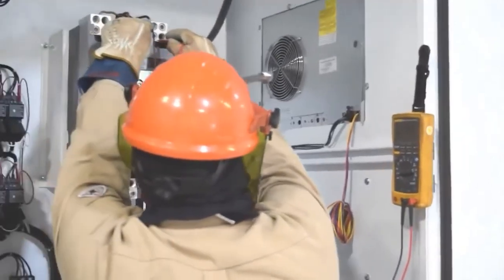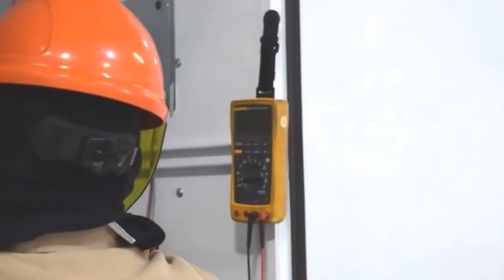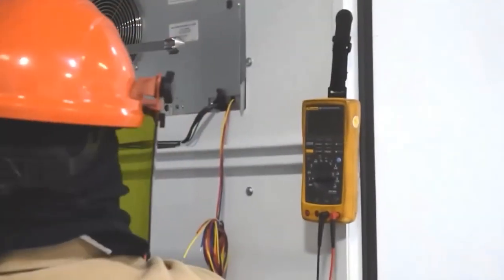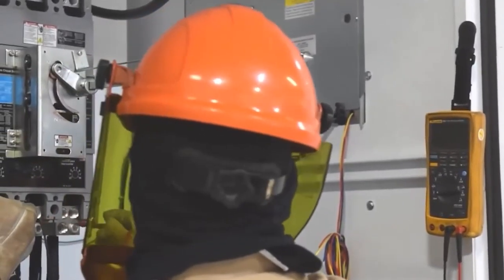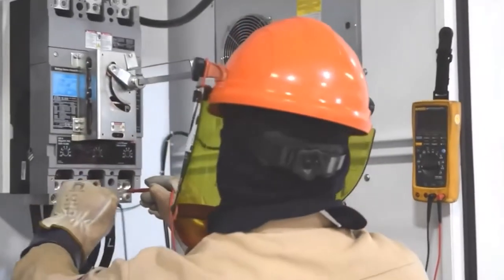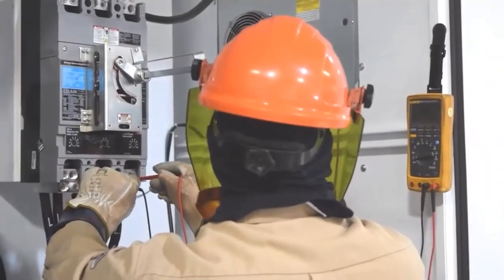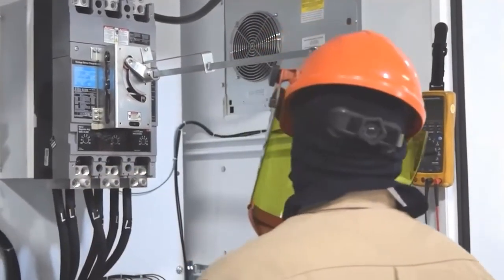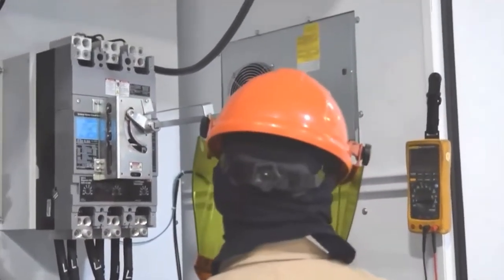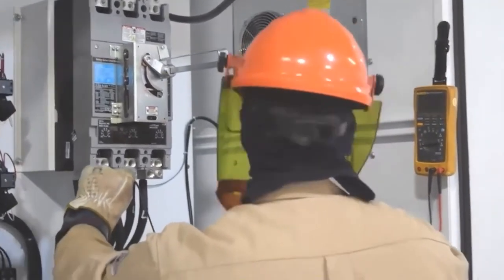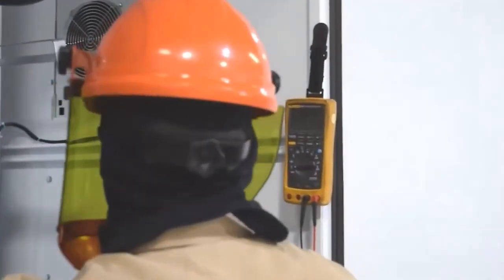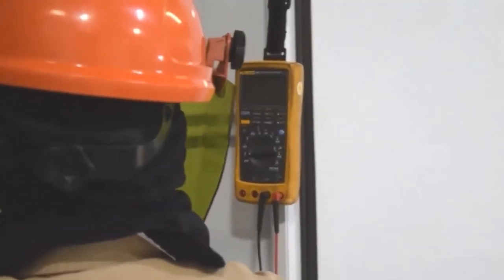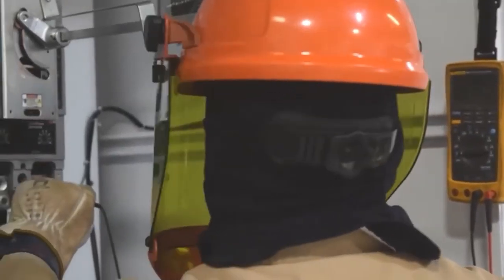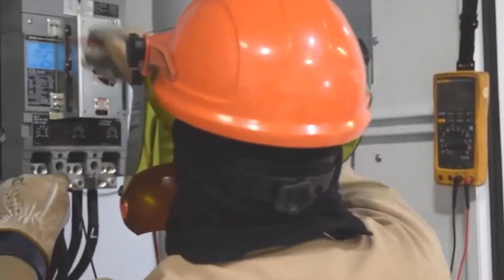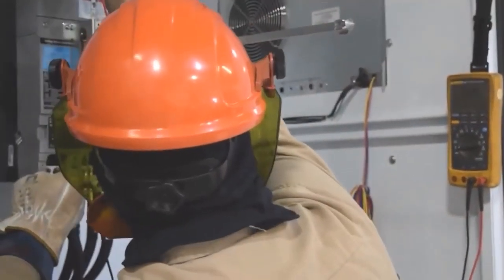So I measure from A to B, B to C, C to A. Should get a pretty normal reading. In our shop, I'm running about 489 or so. I'm going to measure in the front of the breaker and on the bottom of the breaker, just to verify that I don't have any losses across the breaker. And once again, I'm going to measure from phase to ground as well, make sure I have my 277 volts there. In my case, I'm about 285.